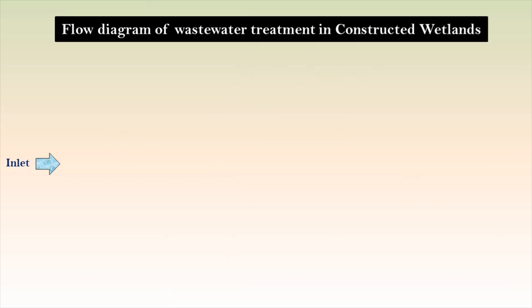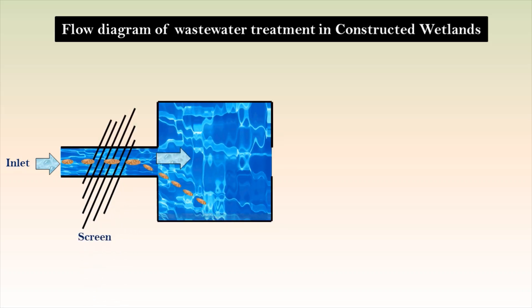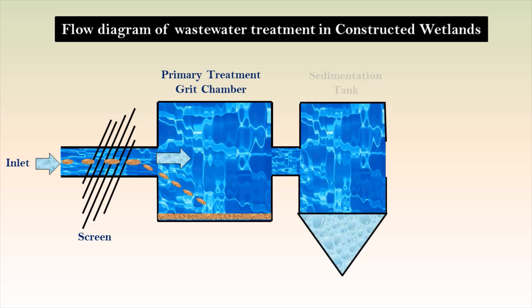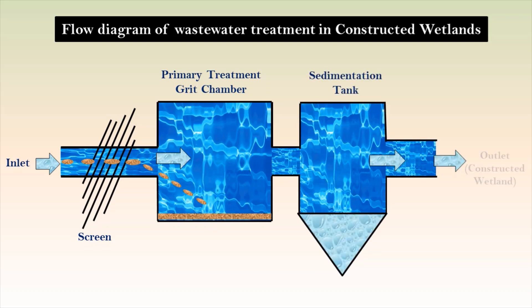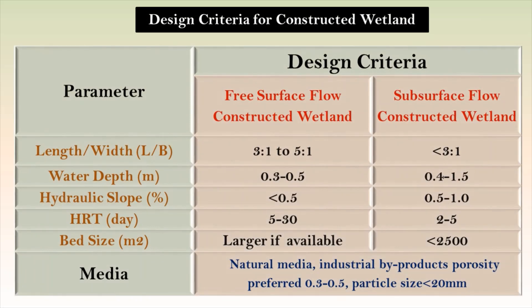A typical treatment scheme of a constructed wetlands-based sewage treatment plant consists of preliminary treatment to remove floating matter and grits, primary treatment to remove excess suspended matter, and secondary treatment using constructed wetlands to remove dissolved organic matter, nutrients, and metals.